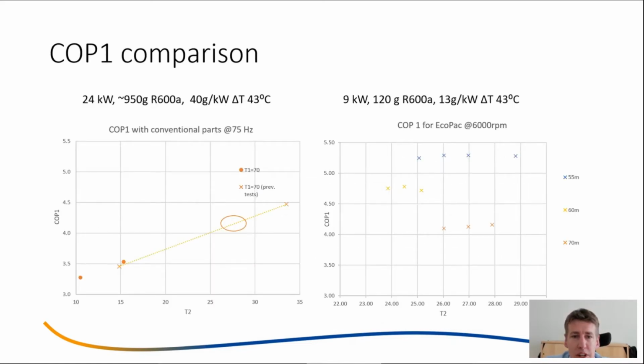So if we look at the comparison here, starting with the diagram on the right, we have condensation temperatures of 55, 60, and 70 degrees. If we only look at the one that is 70 degrees, we have measurements similar to the standard component rig. Then we look at where we are between 26 and 28 degrees. We have marked it with a circle. What we can see is that the COP, or coefficient of performance, is actually more or less the same for both systems.